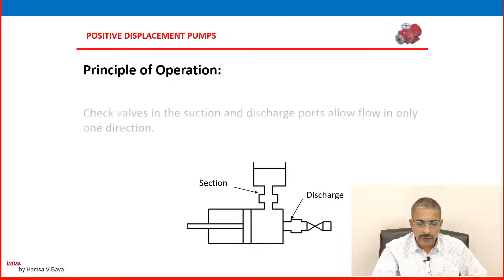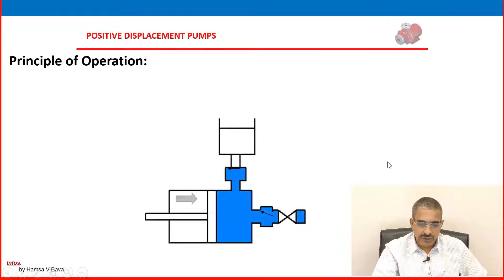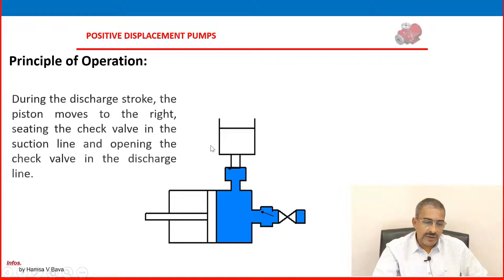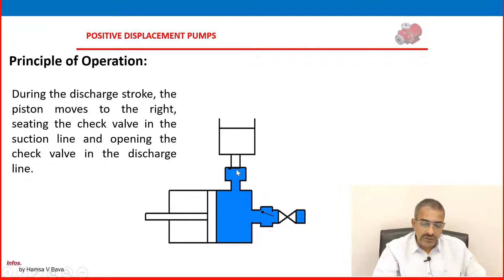Continuing the principle of operation: check valves are present in the suction and discharge ports, allowing flow only in one direction. One check valve is open and the other is closed. During the discharge stroke, the piston moves to the right, seating the check valve in the suction line and opening the check valve in the discharge line. That means only during the discharge stroke will the discharge check valve open and liquid flow to the discharge side, while the suction check valve remains in the closed position.